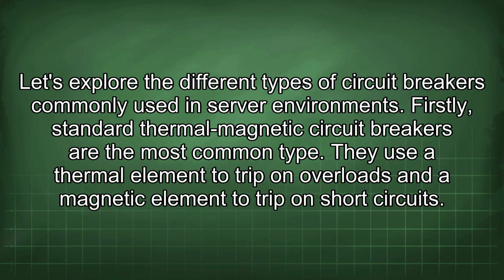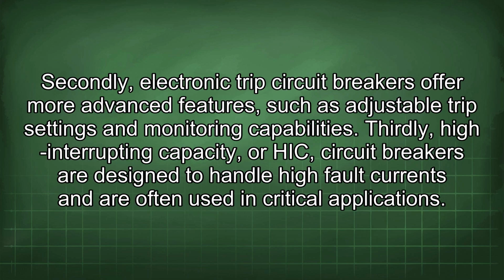circuit breaker. Let's explore the different types of circuit breakers commonly used in server environments. Firstly, standard thermal magnetic circuit breakers are the most common type. They use a thermal element to trip on overloads and a magnetic element to trip on short circuits. Secondly, electronic trip circuit breakers offer more advanced features, such as adjustable trip settings and monitoring capabilities. Thirdly, high interrupting capacity, or HIC, circuit breakers are designed to handle high fault currents and are often used in critical applications.